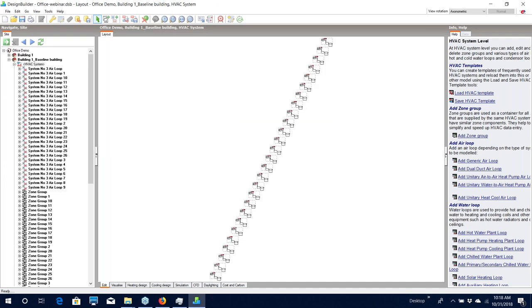Once finished, it will create all of the zonal HVAC systems for the building. There were a number of zones, so it has created about 26 different systems — that would have taken significant time to input individually without the wizard. All these systems have been created using the 90.1 rule set, but it is important that you review the data to make sure Design Builder's choices match your interpretation of the standard, especially checking minimum efficiencies, pumping powers, pre-coil requirements, and heat recovery requirements. In the end, it is your responsibility to make sure inputs are correct before submitting results for review.